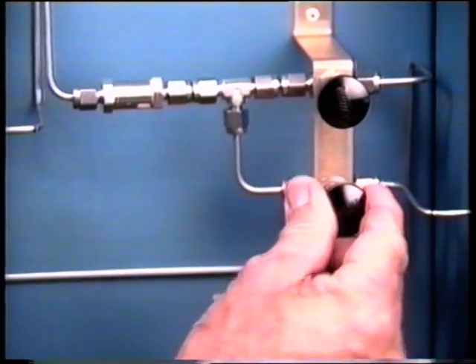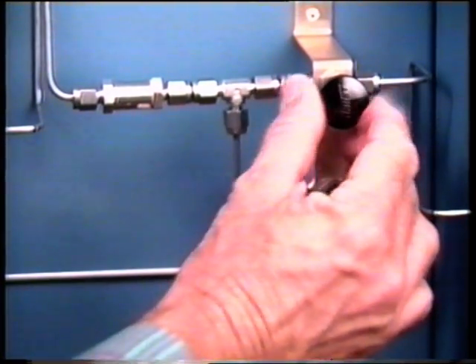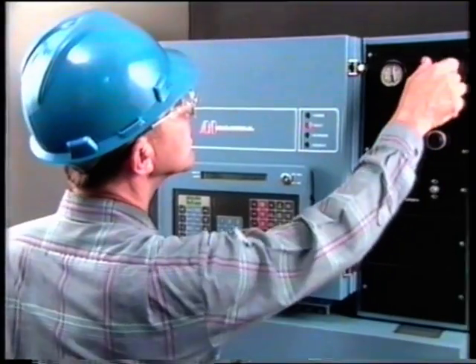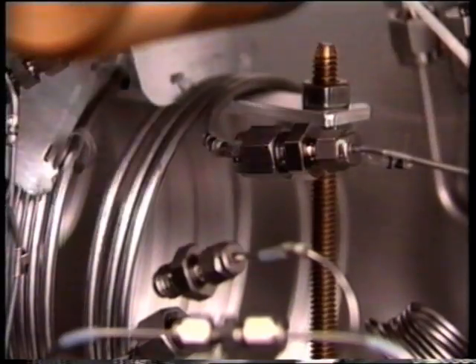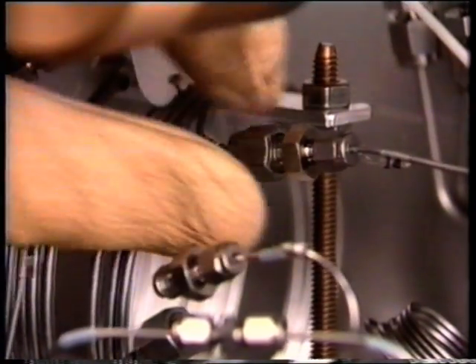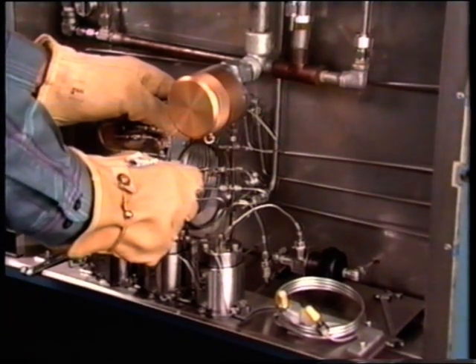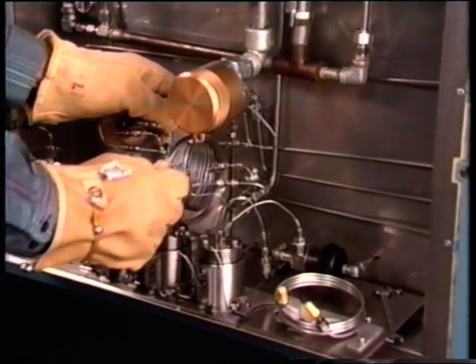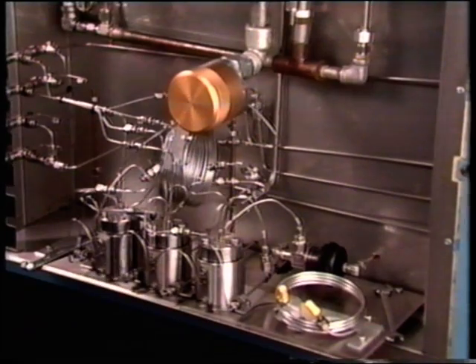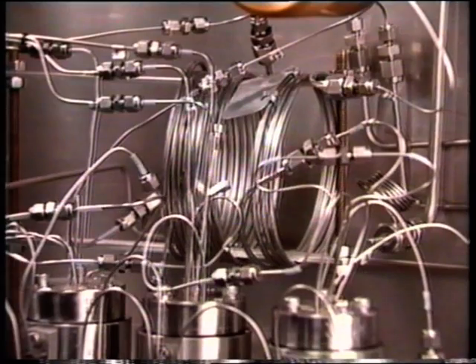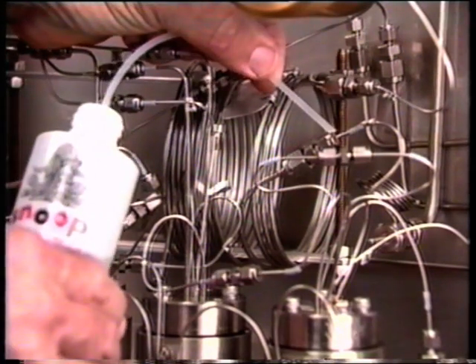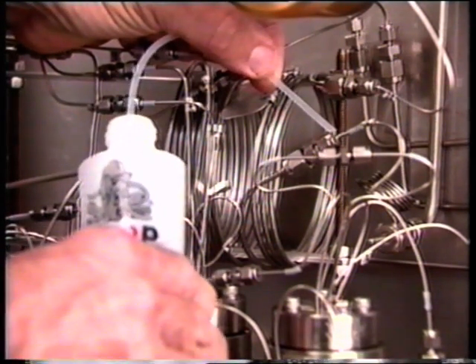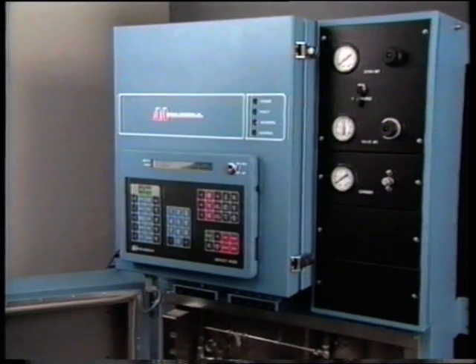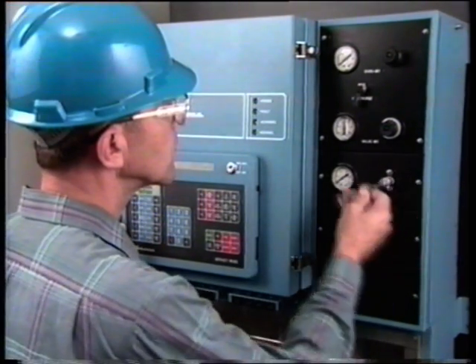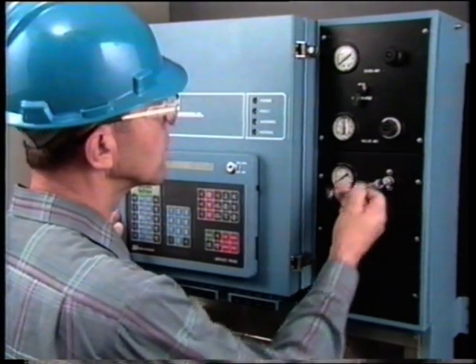When replacement of the column is required, first shut off the sample stream and then the carrier flow. Loosen the column fittings and remove the column from the oven. Install a new column that is an exact replacement of the damaged column and secure the fittings. Restart the carrier flow and check for leaks. If there are no leaks, restart the sample stream and return the gas chromatograph to service.